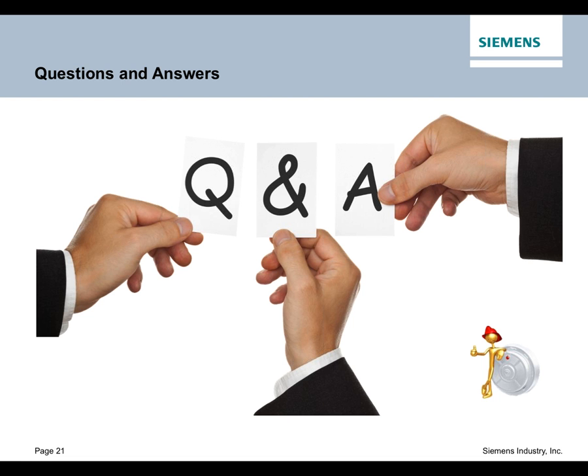There you go. Certainly, sure. Yeah, that is a good practice. In today's world, being able to have a single workstation, a single way for a building engineer, a building manager to be able to see everything that's happening in their building, there's a lot of logic and there's a lot of value to doing that. The systems are going to be parallel. They're going to be installed separately still. Your HVAC, your fire alarm, your fire sprinkler, and maybe even throw the word security in there also. But to be able to bring all of these together into an integrated visualization and a visual integrated control approach is important, as long as it's important to the mission of your building and of your operation. It's not needed in every building, but the more complex the building, the more logical it is to have that integrated approach today to being able to manage things and view things and share that information back and forth.